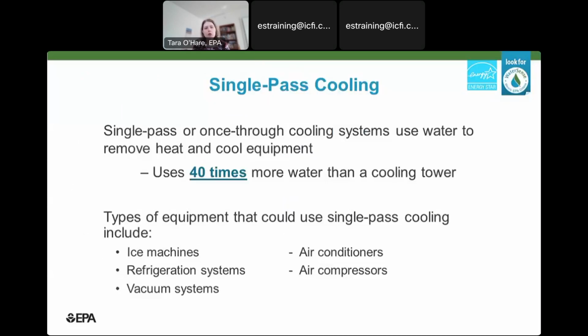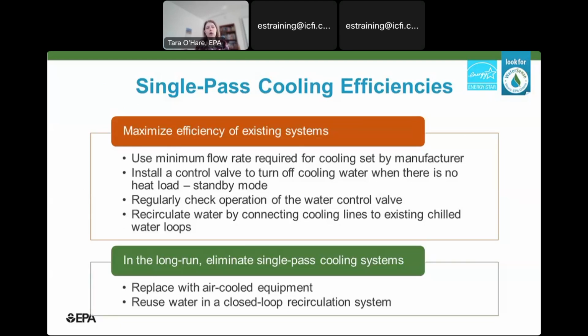So single pass cooling, or once through cooling, basically is where water runs through a fixture or a piece of equipment to remove some heat and cool it down, and it just sends the water through one time and then discharges it to the sewer. And this actually uses about 40 times more water than a cooling tower to remove the same heat load. So some types of equipment that could be using single pass cooling are things like ice machines, refrigeration systems, vacuum systems, air conditioners, and air compressors. So this is something that you want to eliminate whenever possible.